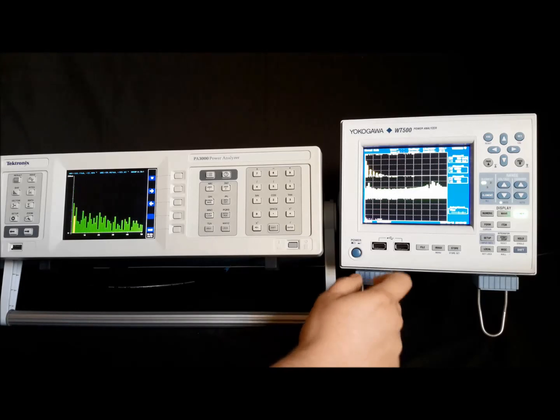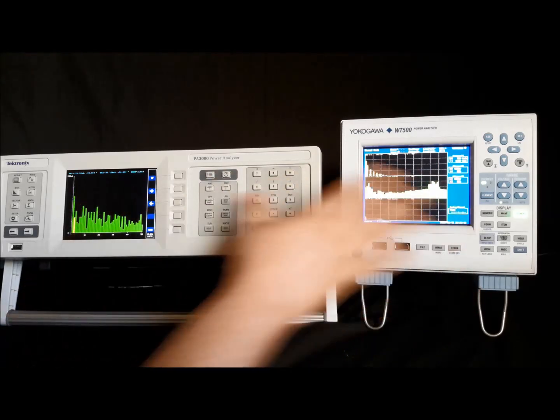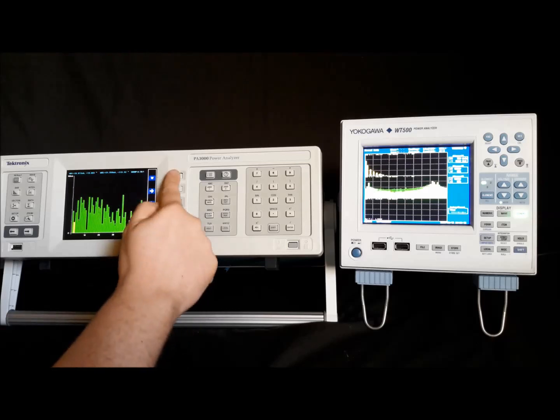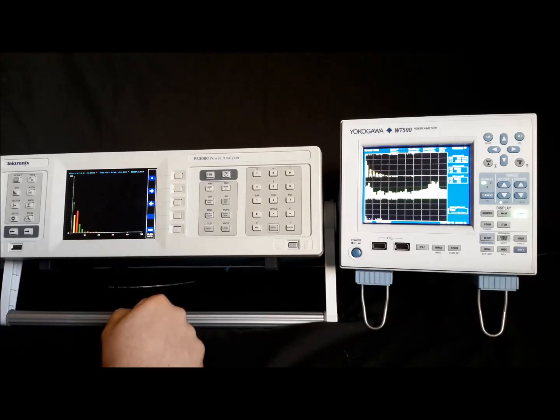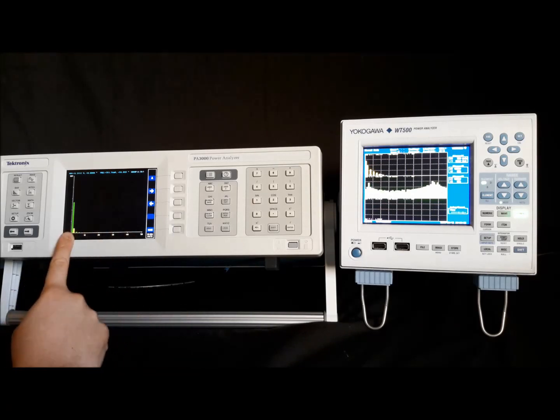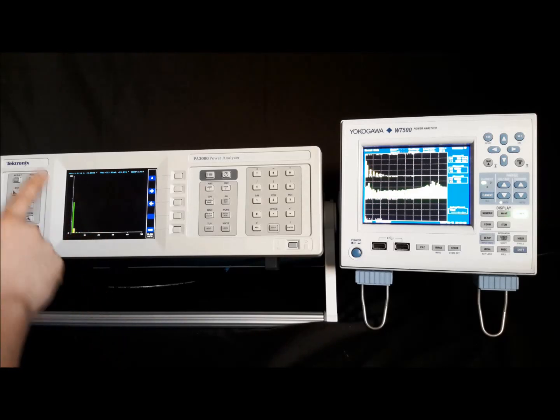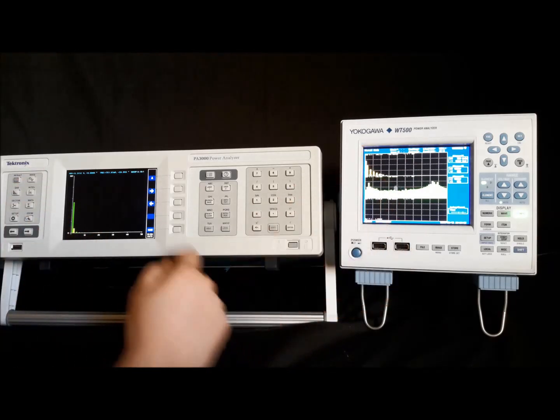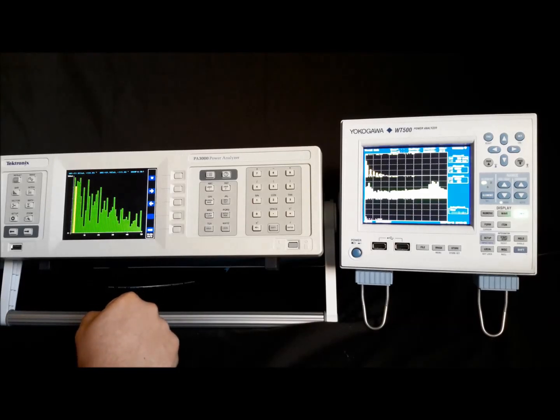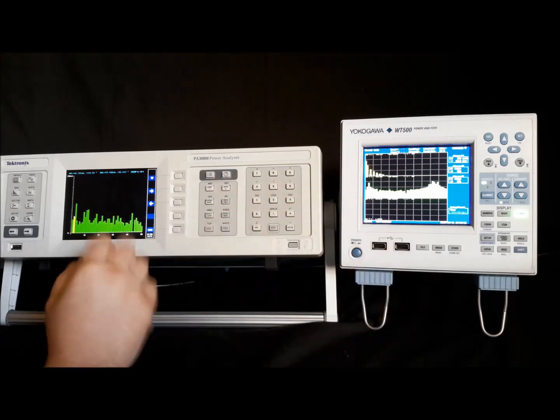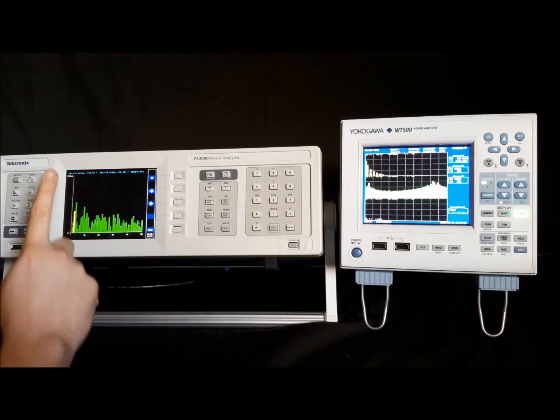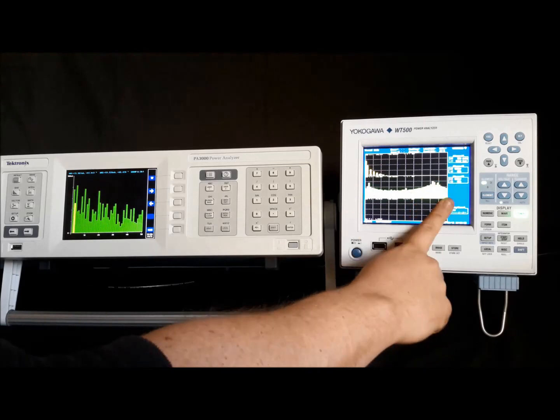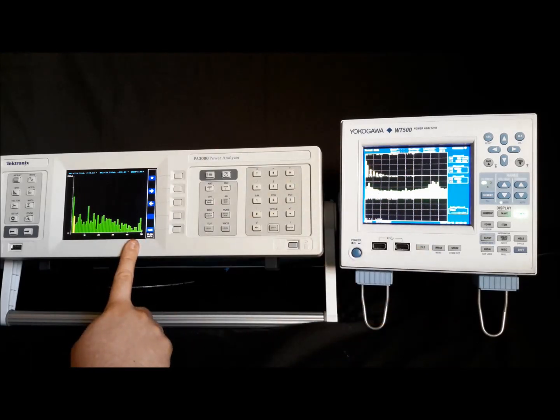So there seems to be a clear difference in looking at the current harmonics. What would the voltage harmonics show? For the sake of scalability, these seem similar - they sweep down on the voltage - but the current harmonics, that's a bit of a concern given such a difference. You see spikes in places on the Tek and not on the Yokogawa, and then spikes on the Yokogawa that aren't on the Tek.